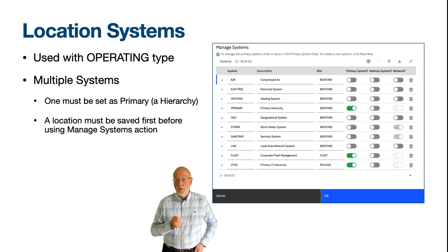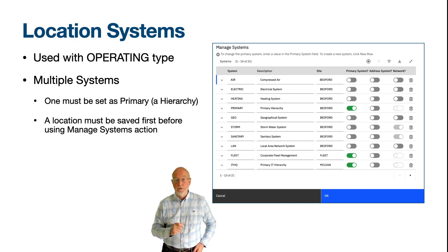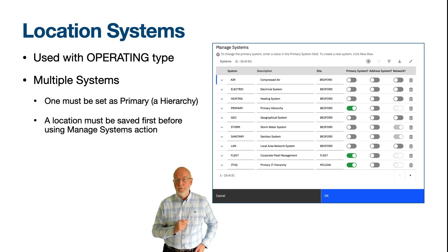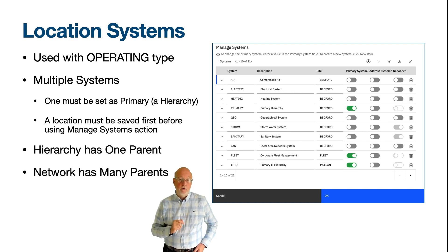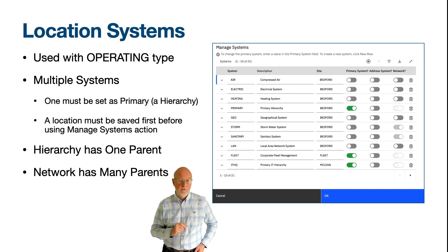It is only locations of type Operating that can be added to a location system, and a location must exist before you can use the Manage Systems action to define your systems, as shown on the right. The first system you enter will be hierarchical and will be marked as a primary system. So the first location you create in a Maximo site should be the location you wish to exist at the very top of the primary hierarchy. In a hierarchical system, each location can only have one parent, except the location at the top of the hierarchy, which doesn't have a parent.